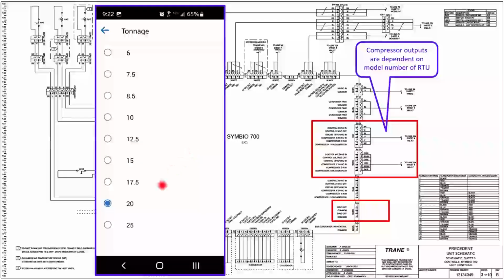Tonnage. Always you want to know what tonnage you have and set it correctly, because that's going to control your compressor 1 or 2. Compressor outputs are dependent on the model number of the RTU.